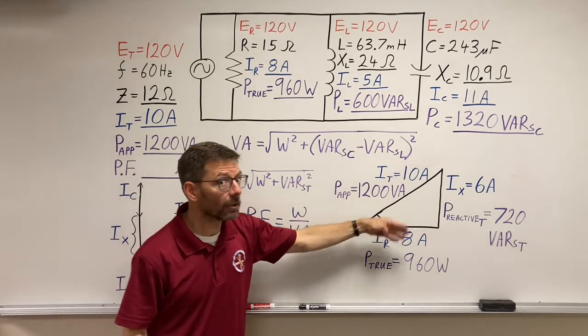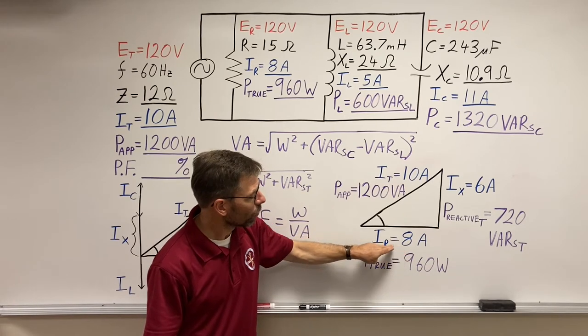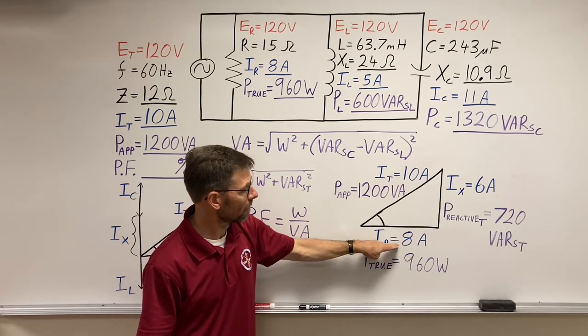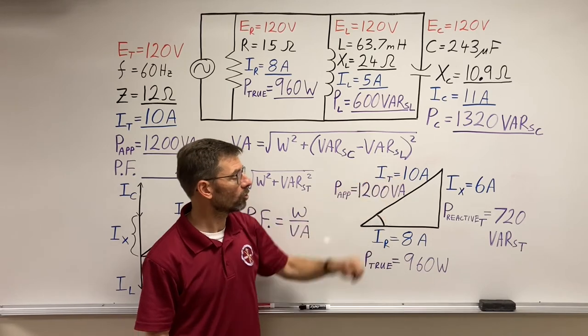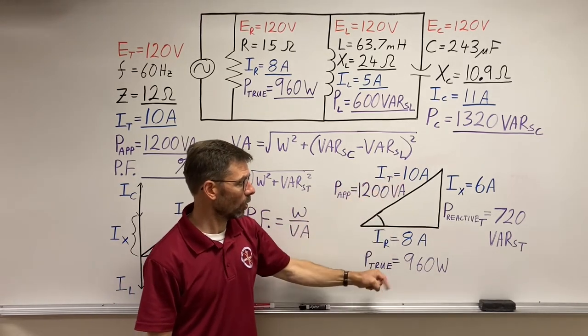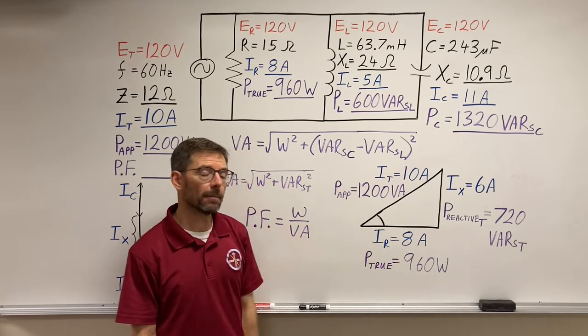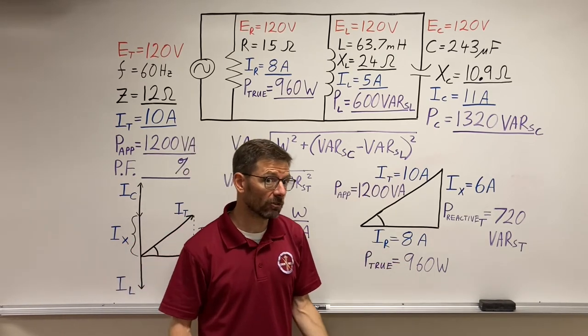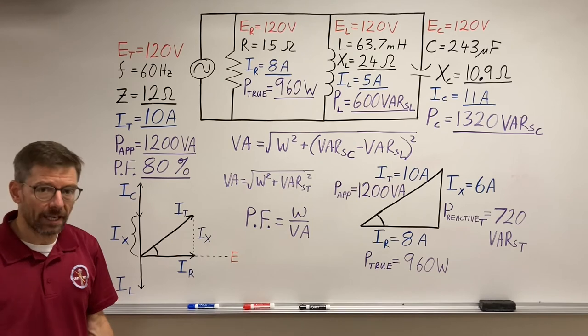We could also, because the triangles are proportional, use my resistive amps over my total amps. And you do either one - 8 divided by 10 or 960 divided by 1200 - and you're going to get 80%.